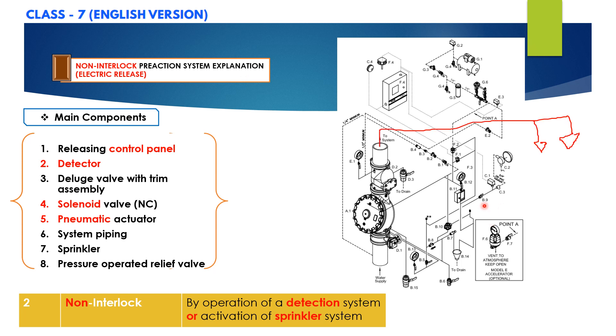In short, a non-interlock pre-action system utilizes an electric solenoid valve controlled by an approved system control panel with a compatible detection system, and also a pneumatic actuator. In the event of damage to the sprinkler piping or sprinklers, the deluge valve will open and water will flow from any opening of the sprinklers and any other opening in the sprinkler system piping.